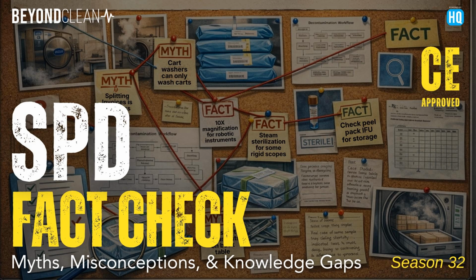If we're using an immediate use sterilizer, it's kind of like using a microwave. We hit a button, it immediately jumps up to a high temp, and when it's off, it comes down without that cooling period. Clinically, what typically happens is somebody grabs it out because they need it right away—it's really warm, they've got those big fireplace gloves, I jokingly call them—and into the OR it goes. It's just like a cold wine glass at home that you put under hot water—that's the end of the optics. That's interesting, now I know why my scopes come down broken. No, I'm just kidding.